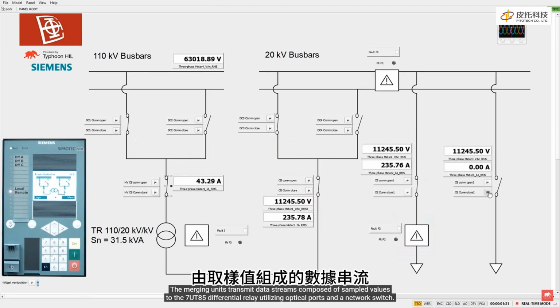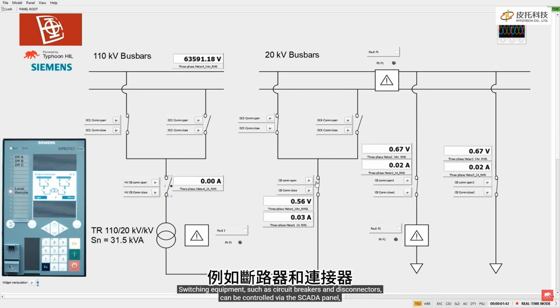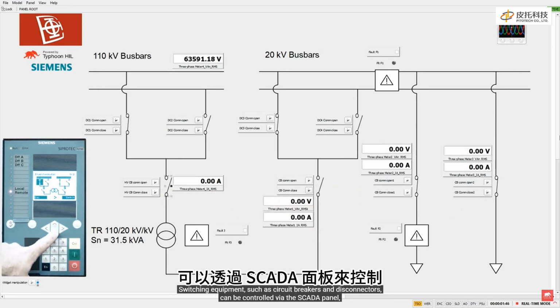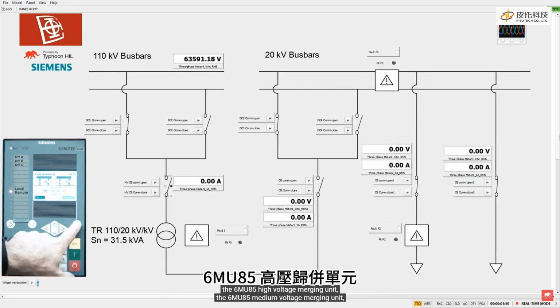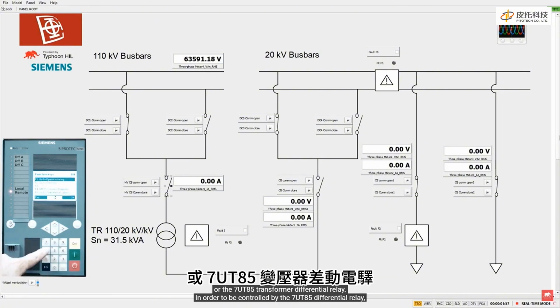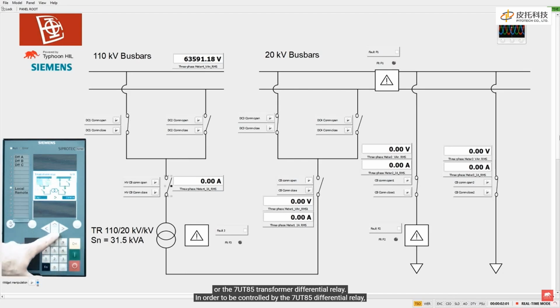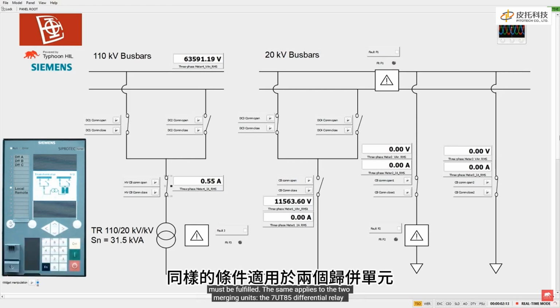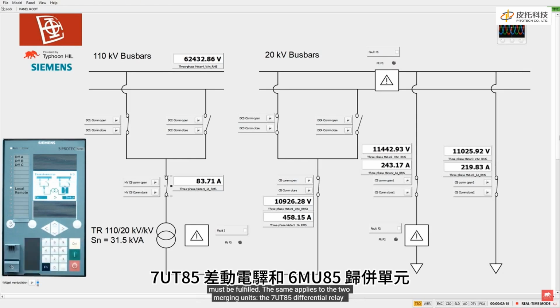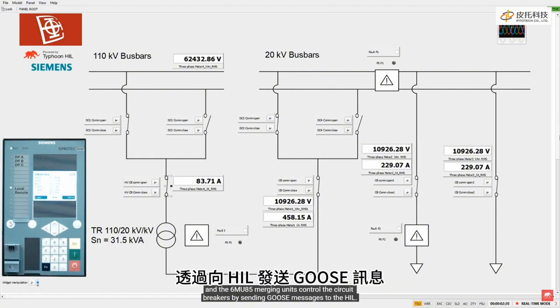The merging units transmit data streams composed of sampled values to the 7UT85 differential relay, utilizing optical ports and a network switch. Switching equipment, such as circuit breakers and disconnectors, can be controlled via the SCADA panel, the 6MU85 high voltage merging unit, the 6MU85 medium voltage merging unit, or the 7UT85 transformer differential relay. In order to be controlled by the 7UT85 differential relay, the device must be in local operation and the conditions for controlling the switching device must be fulfilled. The same applies to the 2 merging units. The 7UT85 differential relay and the 6MU85 merging units control the circuit breakers by sending GOOSE messages to the HIL.